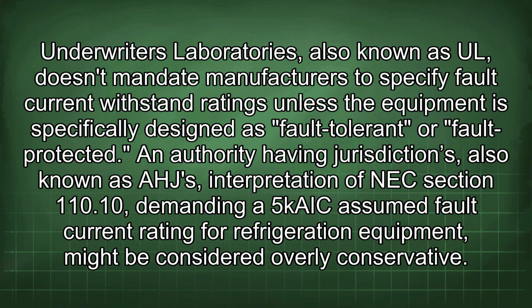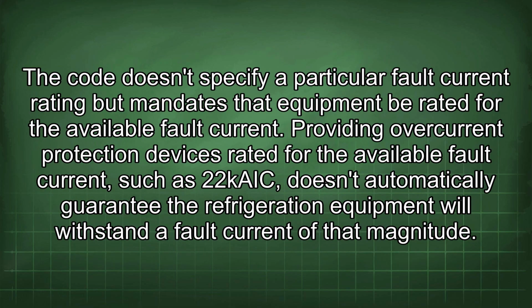Underwriters Laboratories, also known as UL, doesn't mandate manufacturers to specify fault current withstand ratings unless the equipment is specifically designed as fault tolerant or fault protected. An authority having jurisdiction, also known as AHJ, interpretation of NEC Section 110.10 demanding a 5kAIC assumed fault current rating for refrigeration equipment might be considered overly conservative.